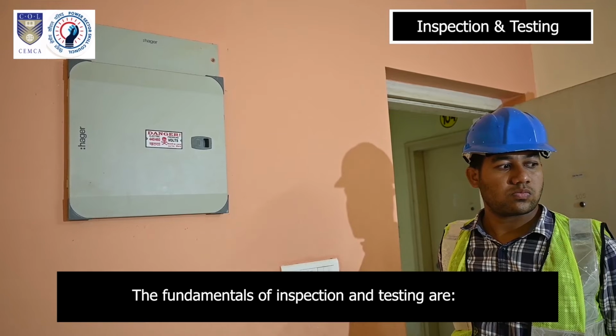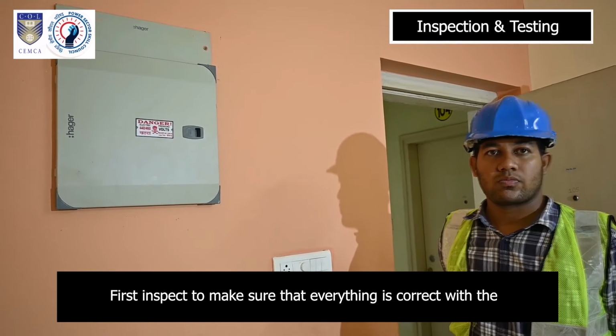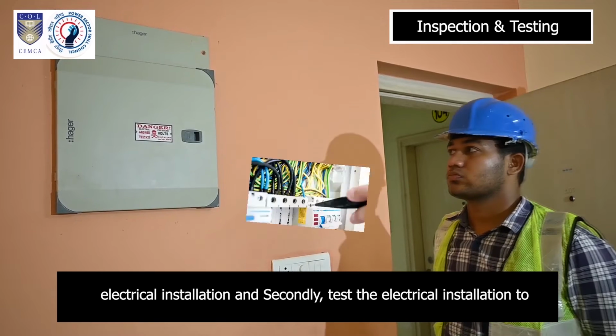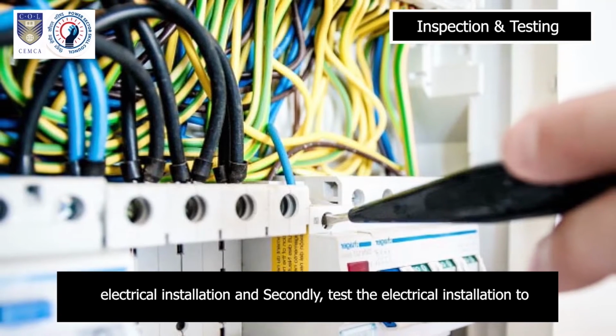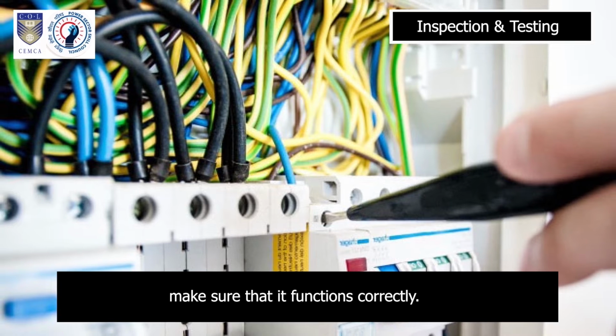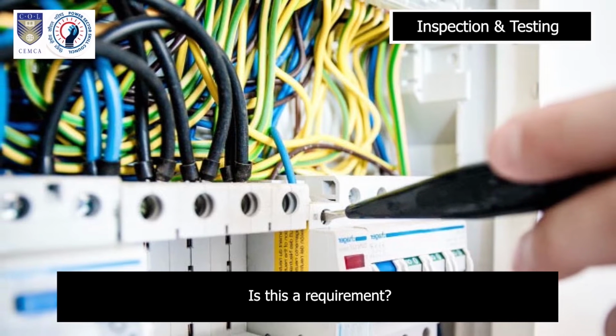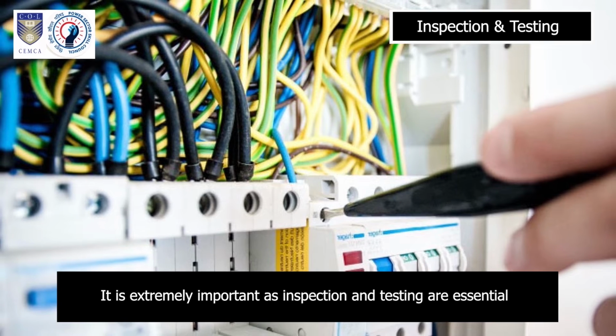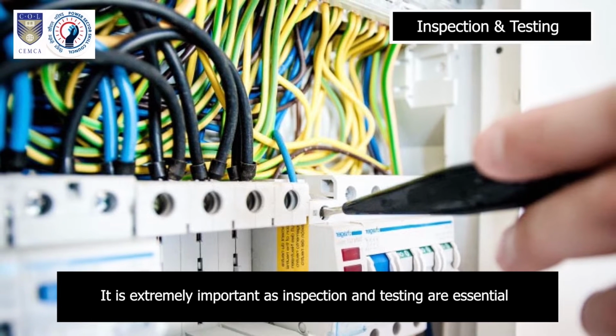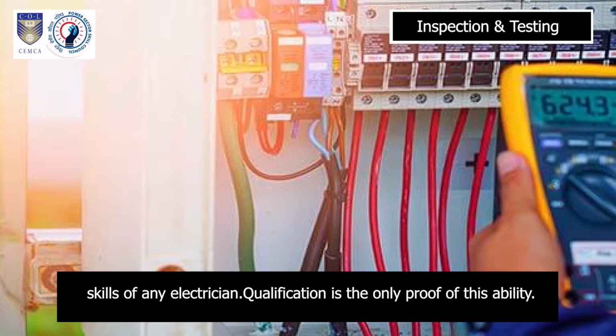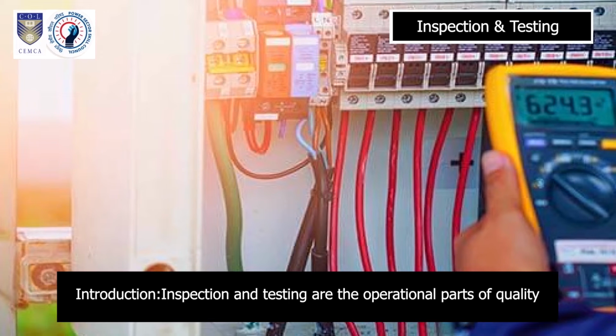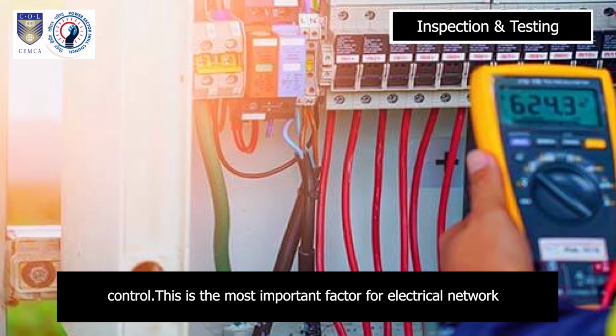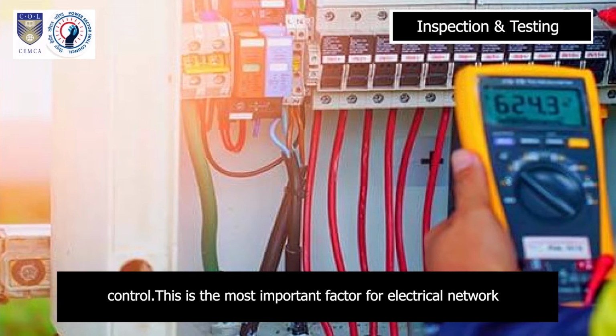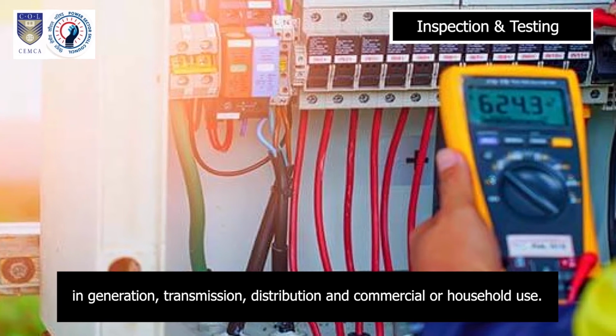The fundamentals of inspection and testing are: first, inspect to make sure that everything is correct with the electrical installation, and secondly, test the electrical installation to make sure that it functions correctly. Is this a requirement? It is extremely important, as inspection and testing are essential skills of any electrician. Qualification is the only proof of this ability. Inspection and testing are the operational parts of quality control. This is the most important factor for the electrical network in generation, transmission, distribution, and commercial or household use.